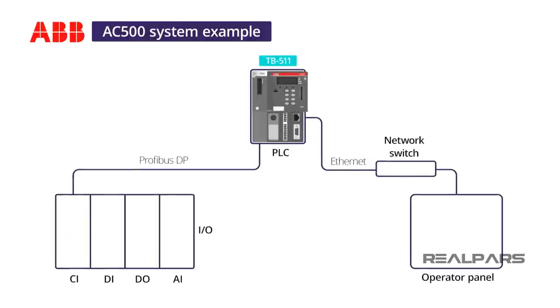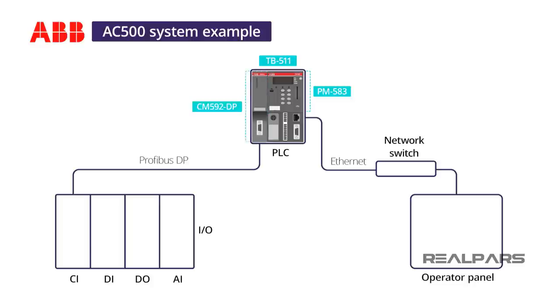I choose a TB511 terminal base to support the CPU's Ethernet port and to provide one additional communication card slot for a Profibus DP communication card. I select a CM592DP Profibus DP Master communication card to fit next to the CPU in the terminal base. This Profibus interface has a standard 9-pin Profibus connector and supports baud rates from 9.6 kilobits per second to 12 megabits per second.